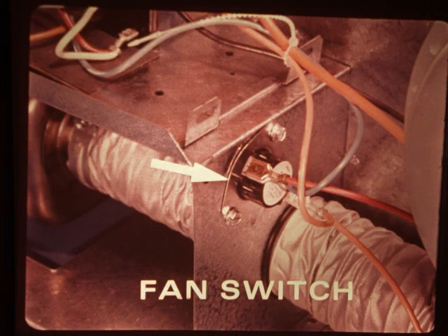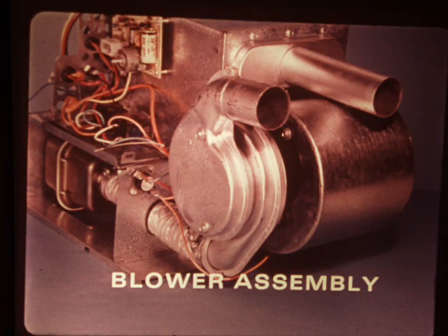The fan switch controls the operating sequence of the furnace blower. You'll hear it snap closed when it heats up after about 1 minute of furnace operation. When the thermostat is satisfied and shuts down the burners, the fan switch allows the blower to keep running for a short time. When the combustion chamber cools, the fan switch contacts open, shutting off the blower. The blower assembly has one motor that drives both the combustion air and circulating air blower wheels. The assembly is sealed, so there's no passage of air between the two systems.